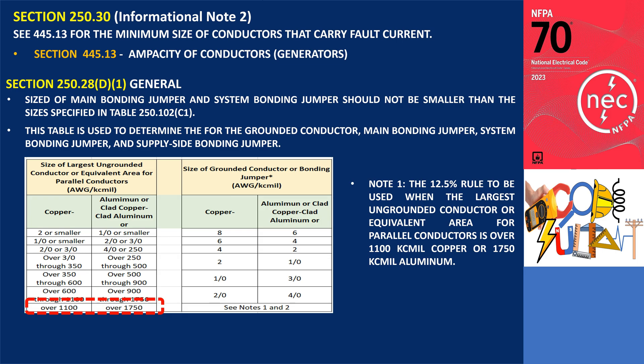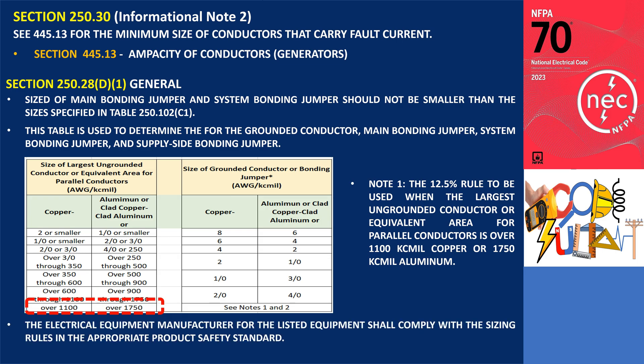Furthermore, a main bonding jumper furnished as part of listed service equipment can also be used as the system bonding jumper for separately derived systems, without the need for any additional calculations, as discussed in 250.28.